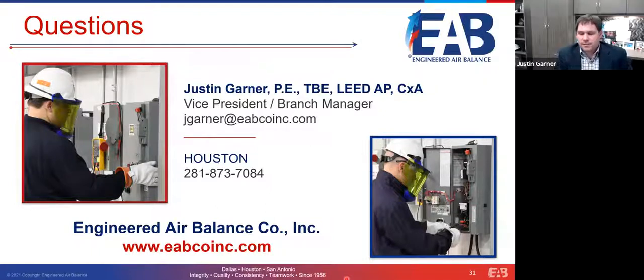No, that's very good information, Sam. I appreciate whoever submitted that, because you're right, we did not cover that today. But it is absolutely correct. NEMA may allow that. Obviously, anytime that you go above 60 Hertz, the nameplate rating on the motor, I would challenge anyone that sees that particular instance to ensure that the motor and whatever it's connected to were designed to operate that way. Just because you can run a motor over 60 Hertz doesn't mean the fan that's connected to it is rated to go above whatever the 1780 RPM, if it's a 1780 RPM motor. So just because you can do it, by NEMA standards, and the drive will let you do it, doesn't mean it's always a good idea, but the statement that was submitted is absolutely correct.